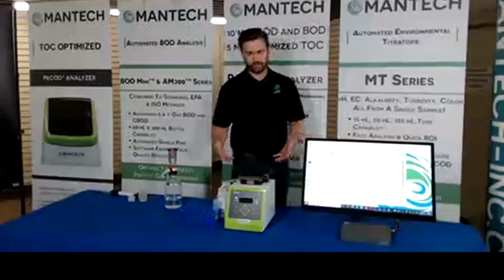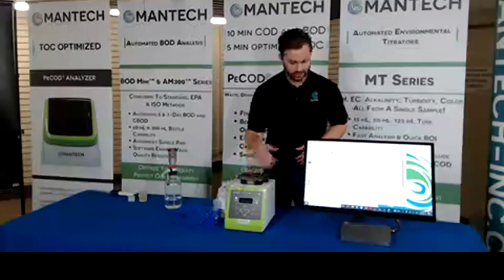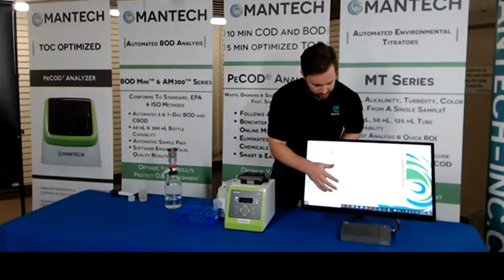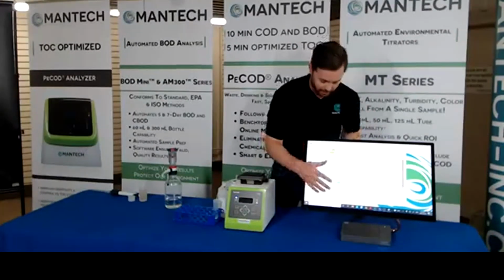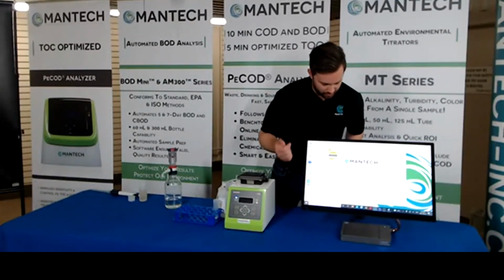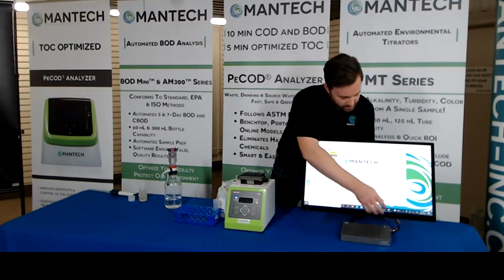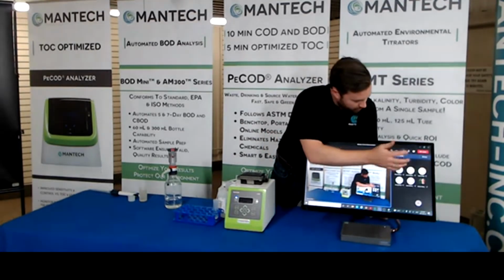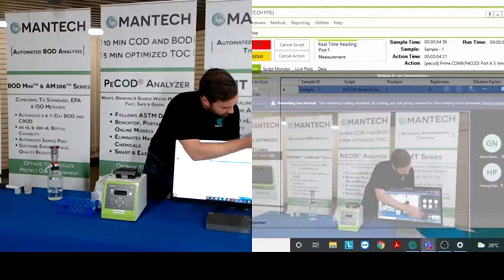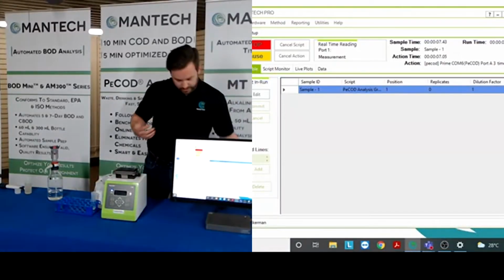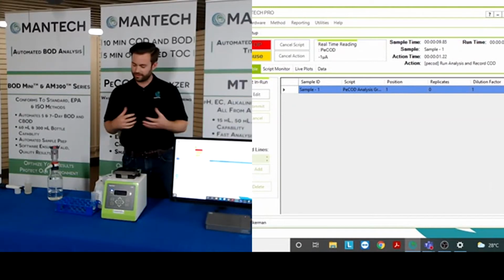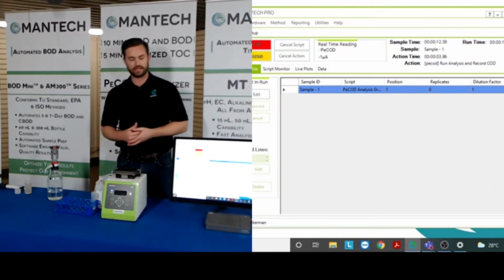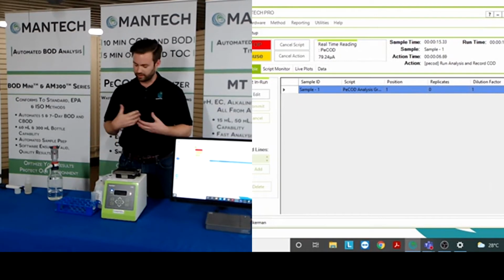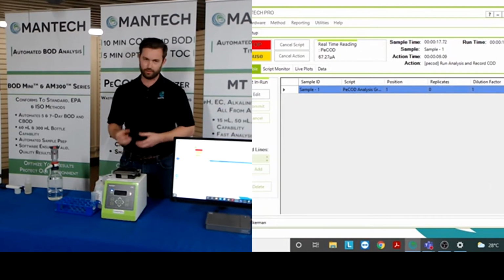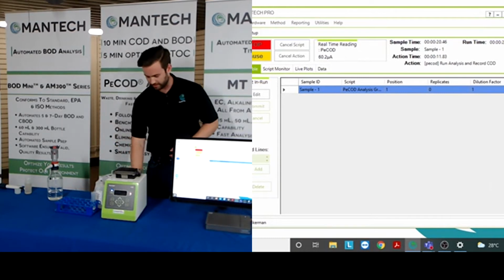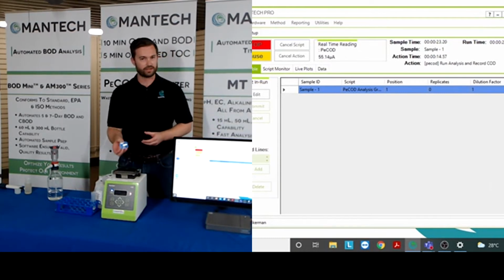Now I could run it off of the touchpad here on the instrument, but I'm actually just going to come right over onto our computer here to make it even easier. Same thing, just a touch button there, and then I just start it right up. And as this is going, I'm going to turn on my screen sharing here so that you can see that as it's going. You should be able to see the software and the hardware going. So right now, PeCOD's just sucking in that sample. We call it priming, bringing it so it's fully brought into the sensor, which is actually doing the work for the PeCOD. So got kind of an example of one of those sensors right here.